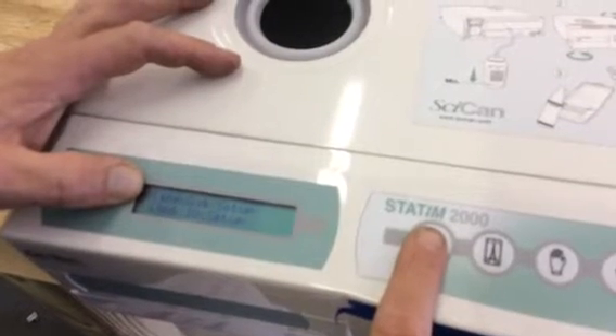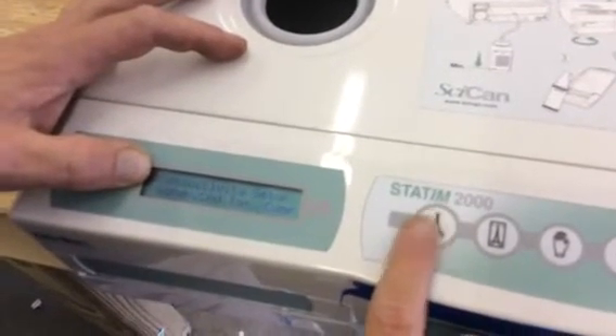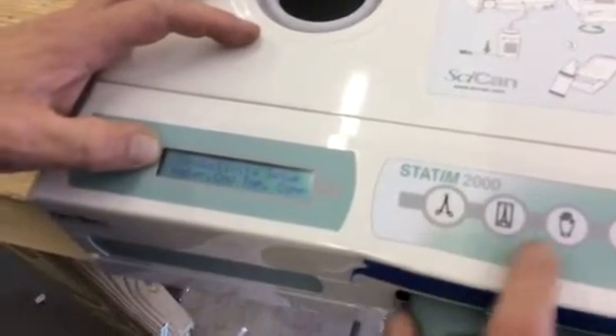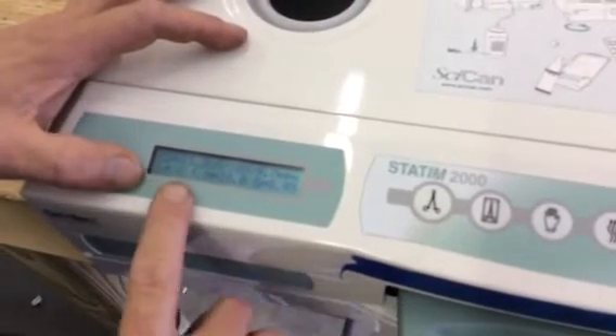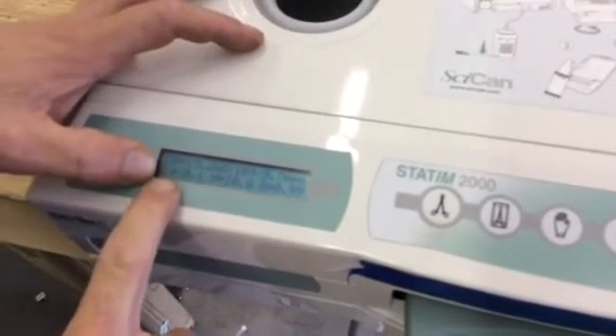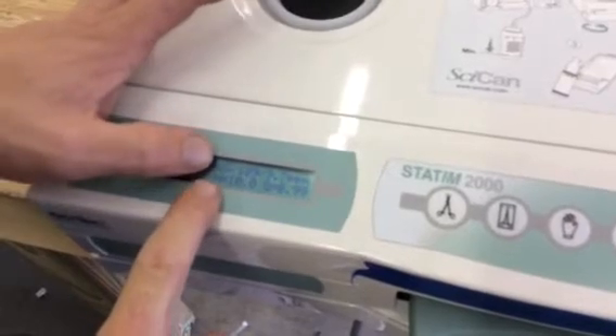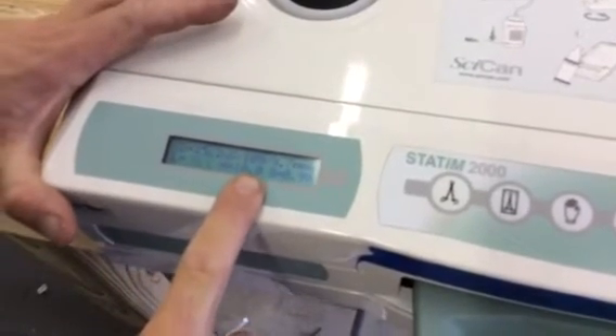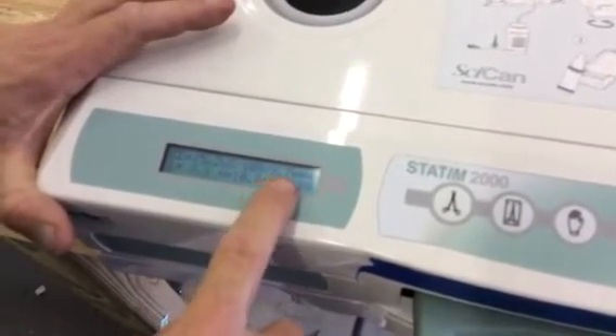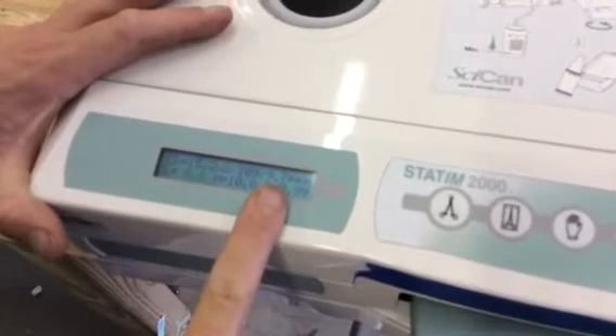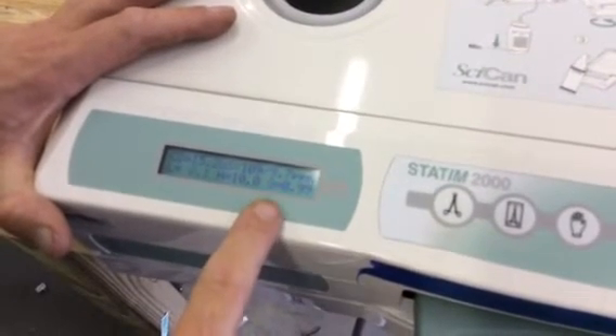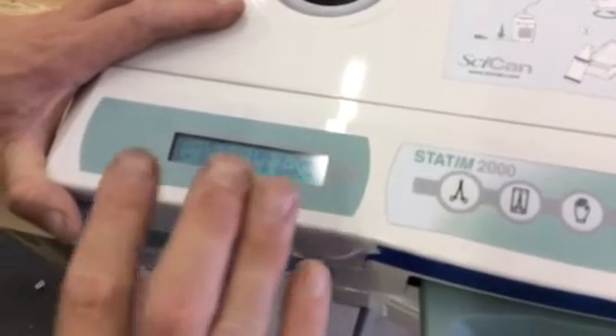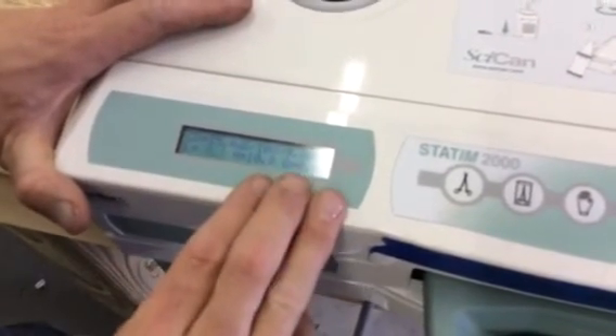We are going to scroll up until the arrow reads conductivity setup. Then we are going to hit the glove. When you get there, the low that the water can be is at 0.1 parts per million. The high is 10.0. In this case, it's 9.7 parts per million. So basically, on this machine the water quality is acceptable.